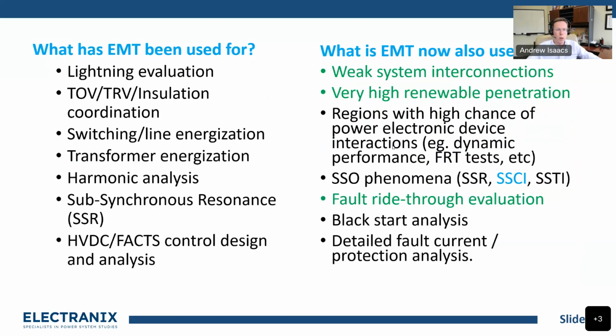So what has it been used for? For the past decades, we've been using EMT for lightning, for TOV studies, insulation coordination, all those special studies that require really fast looks at transient behavior - switching, energization, harmonics, subsynchronous resonance phenomena, because you need to be able to look at non-60 hertz quantities in the subsynchronous range. Control design and analysis was one of the original applications for the PSCAD tool. PSCAD is kind of our tool of choice, but there are competing products that do the same thing.